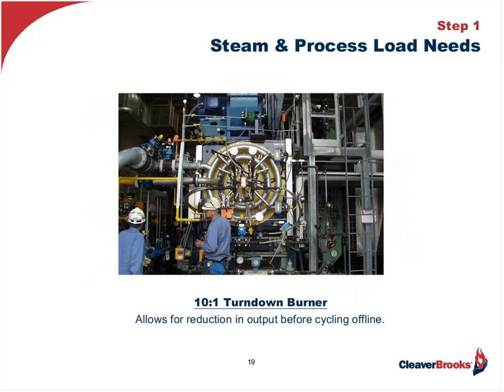The next thing I would specify is a 10-to-1 turndown burner. In the case of a 200,000-pound-an-hour boiler, a 10-to-1 burner will allow the boiler to reduce its output to 20,000 pounds an hour before cycling offline — you simply divide by 10. This will be critical for tracking the load during process variability and during those high-demand months when the plant is processing the seasonal vegetable pack, adding another 40,000 pounds an hour to the load. Along with the turndown, you want to make sure the boiler can respond to ramp rates. A typical ramp rate for an industrial water tube boiler is 20% of the MCR, or maximum continuous rating, per minute. Specify that the boiler is capable of 20% ramp rate as well as 10-to-1 turndown.